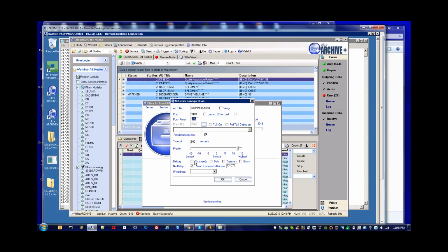Sometimes it depends on the sending device. If the sending device doesn't do an association close cleanly, and it keeps the association open forever like Amicus does, you can't use the gateway because the study will never close. Right, but they should handle that when they implement it. Yeah, but I'm talking more about when they bring a new device in. They upgrade their CT scanner, or get a new ultrasound device.